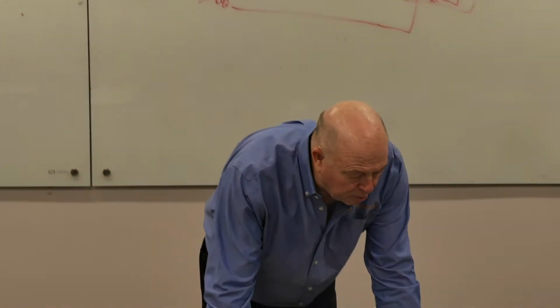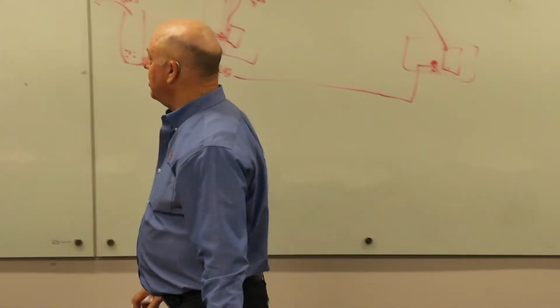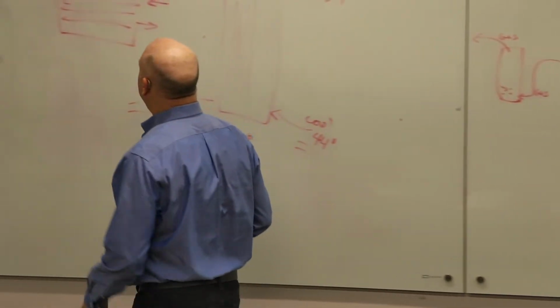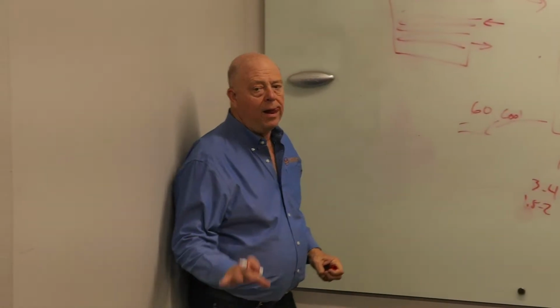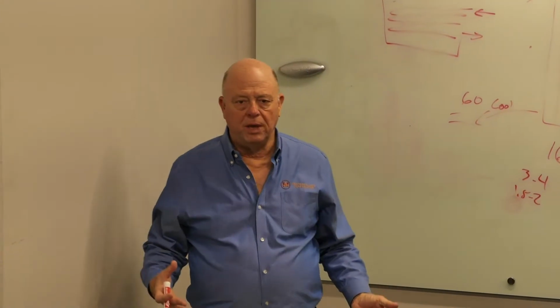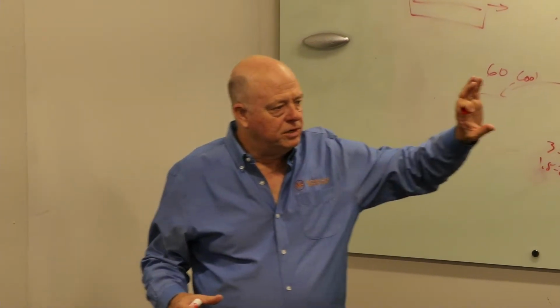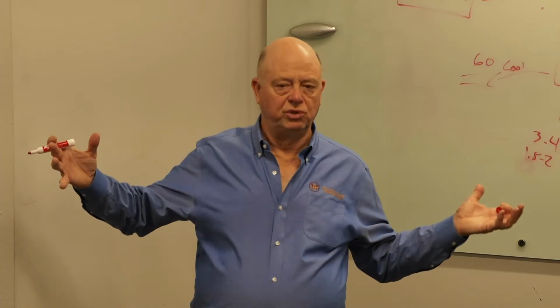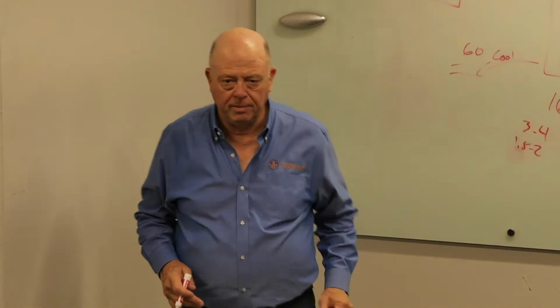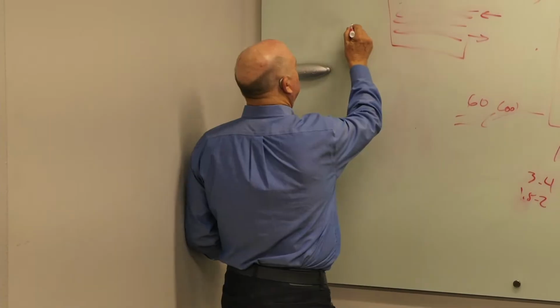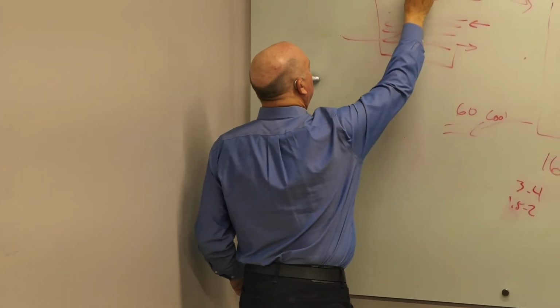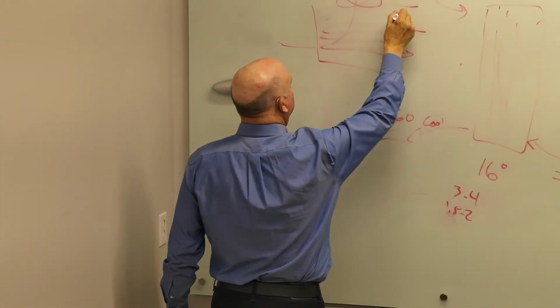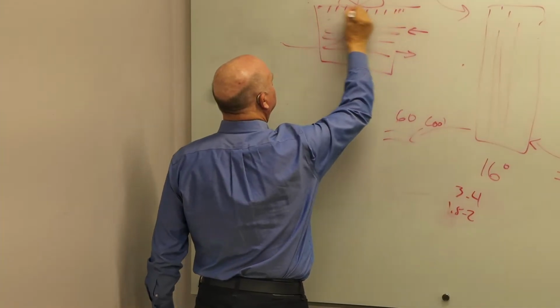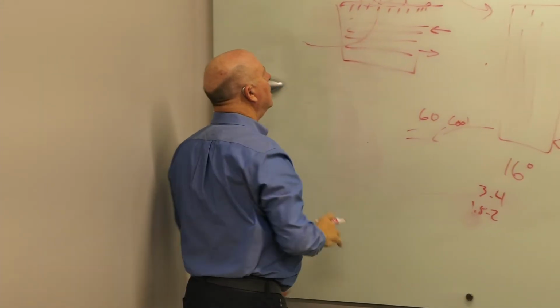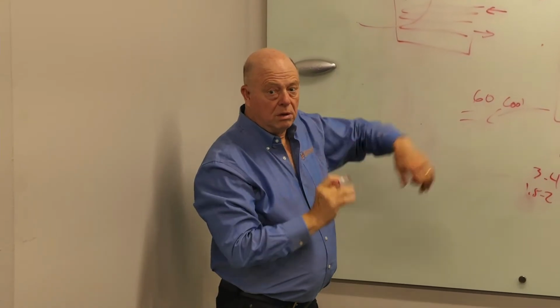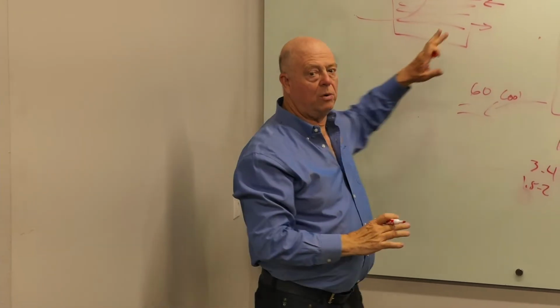So we talked about approach there. Another example, every heat exchanger has an approach. In this one, we haven't talked a lot about wet bulb yet, but wet bulb is the moisture level, if you will, of the outside air. Air gets pulled in on this tower. The water is dripping down from up above, usually from some trays. That's counterflow. The water's coming down, the air is going up.